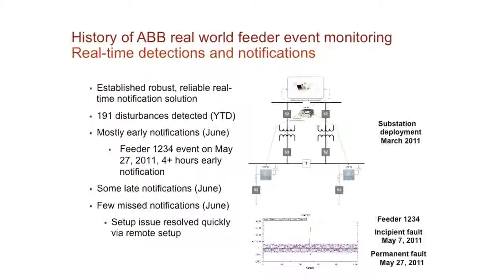Now, we did have just a little feedback. Most of the 191 disturbances we detected were early. What that meant was the email with the information about that cable fault - you can see how short-lived that is, high current, very short-lived - got to the dispatcher before the first customer call. So they actually had knowledge and information about a cable fault in their system that caused an outage before the first customer called.